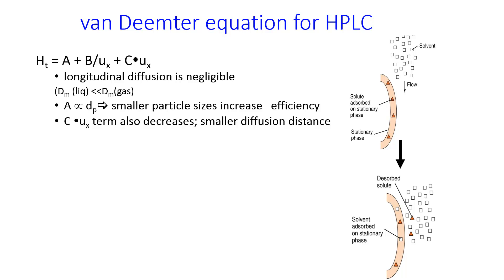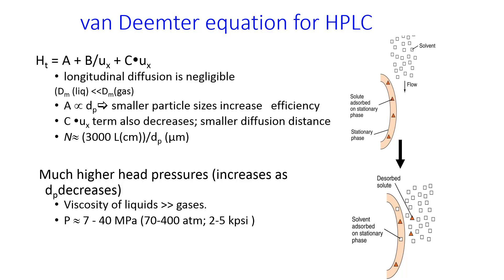For an HPLC column, the number of plates scales with this particle size, the d_p, particle diameter, and with the length of the column roughly as 3,000 times the length in centimeters over the diameter of the particles in micrometers. This is a rough estimation, but it's usually pretty close. Like I said, the pressure increases a lot as the particle size decreases, and so typical pressures for an HPLC are roughly in the range of hundreds of atmospheres. A lot of pressure is required at an optimal flow rate of about one milliliter per minute. You can see this if you plotted out the Van Deemter curve. It would have a minimum of about one milliliter per minute.